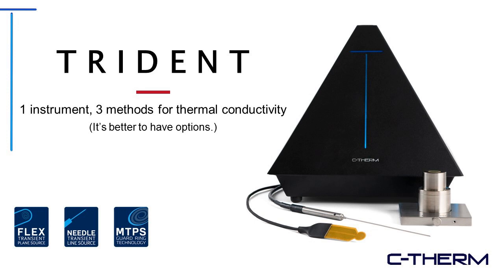I'll describe a little bit of some of those differences amongst them, but we have the Flex Transient Plane Source, sometimes called TPS, or a hot disk style sensor. We have the needle transient line source sensor in this platform. This is sheathed in stainless steel, very, very robust. And we have the MTPS, Modified Transient Plane Source. This is a single-sided sensor. It's sealed, so it's perfect for testing liquids as well as solids, powders, pastes. It's our most versatile and easiest to use sensor, offering the best sensitivity and precision.